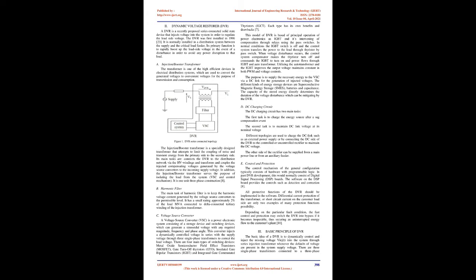The transformer is one of the high-efficient devices in electrical distribution systems, which are used to convert the generated voltages to convenient voltages for the purpose of transmission and consumption. The injection/booster transformer is a specially designed transformer that attempts to limit the coupling of noise and transient energy from the primary side to the secondary side.